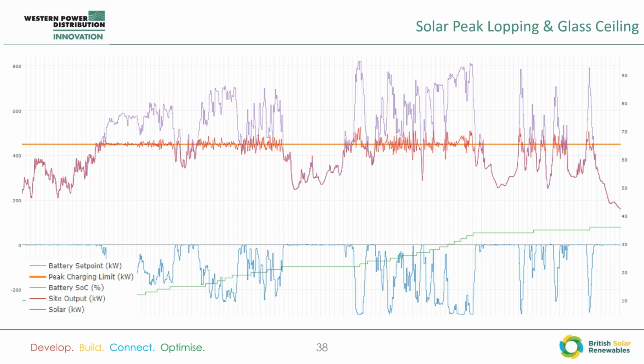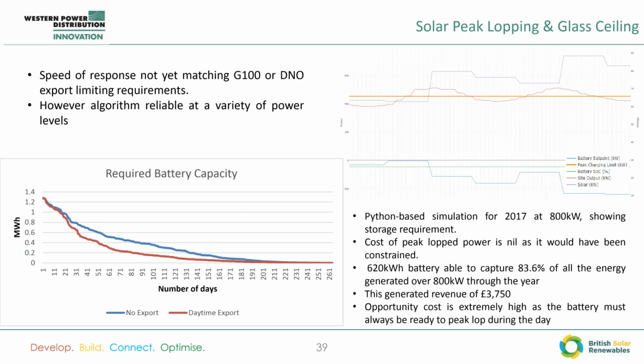I would say that moving forwards, the algorithm needs to be optimized, but it wasn't specified to comply with G100 export requirements because there was no export limit on this site. So I think as an early example of peak lopping, it demonstrates it's working quite well. Going forwards, as I say, batteries respond in less than half a second to frequency response information, so it shouldn't be an issue to make it respond to the solar within the required 5 seconds.